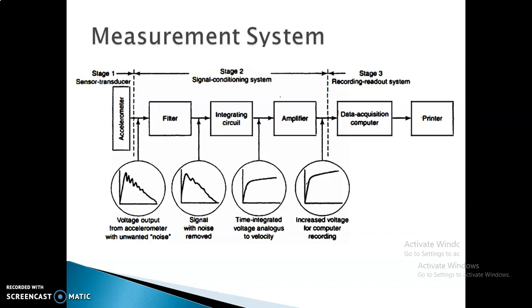The periodic signal from the accelerometer comes with noise. To eliminate the noise, we go to the filter section — after filtering, the noise is removed. Then the signal goes into the integrating unit, which consists of a capacitor that reduces noise and gives a smoothed curve. Since the signal is very low, we go into the amplifier to increase the strength of the signal. Finally, it goes into data acquisition and computer — this is the presentation/recorder part.